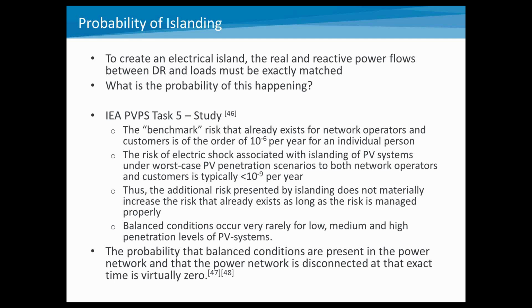So the outputs of this particular study basically said that there's a benchmark risk that already exists for network operators and customers that's on the order of 10 to the minus 6 for any individual person. And then looking specifically at the risk of electrical shock associated with islands under worst case PV penetration scenarios, it was typically less than 10 to the negative 9 per year. So a number of orders of magnitude difference, because you have to maintain this matched real and reactive power case.